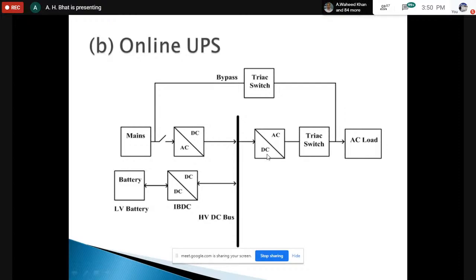And this inverter, it is a PWM voltage source inverter. It converts DC into AC and feeds that AC to the critical load. But in case of modern UPS, which use this dual active bridge DC to DC converter or isolated bidirectional DC to DC converter, what is done is that power comes from the mains.